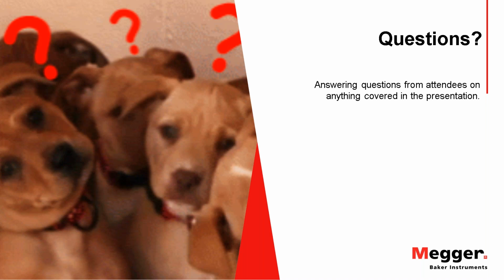Okay. The next question is, does high voltage testing damage my winding? So potentially, I guess, is the most honest answer, but here's the thing to keep in mind. As I mentioned earlier in the presentation, the highest operational voltage stress can be upwards of 4 times nameplate, and that occurs anytime there's a breaking of the circuit. The making and breaking of the contactors produces inductive kick voltage, which is stressing your insulation system. When it does this, it could produce arcs, and it definitely is causing insulation damage during those switching intervals.